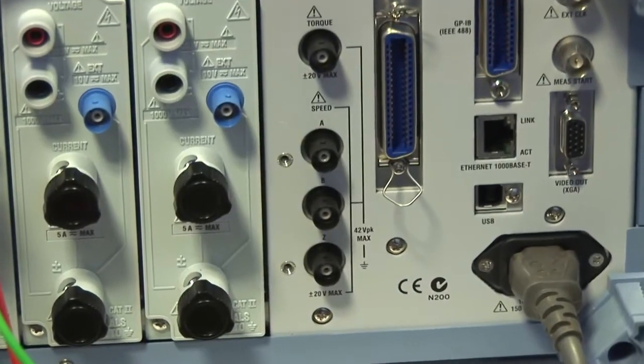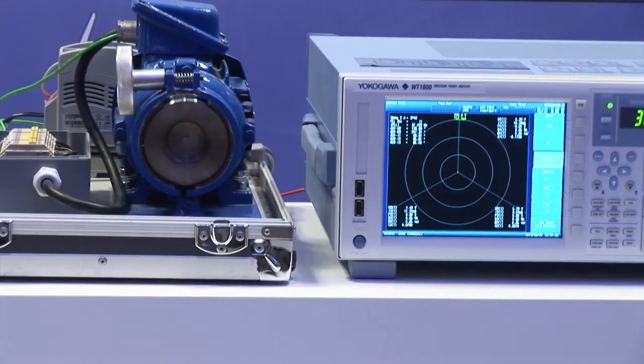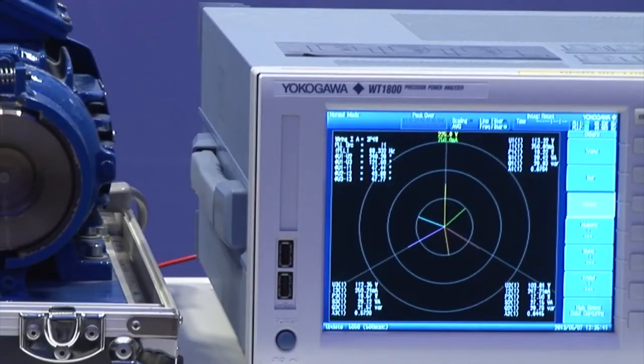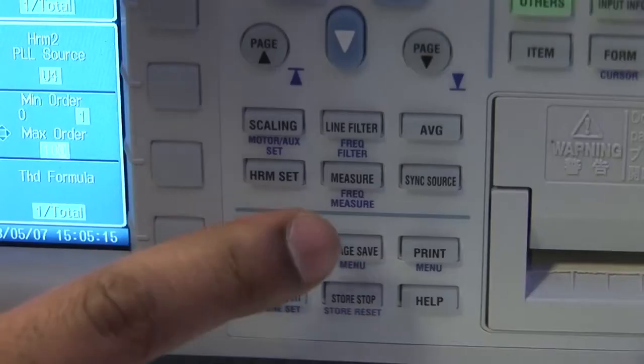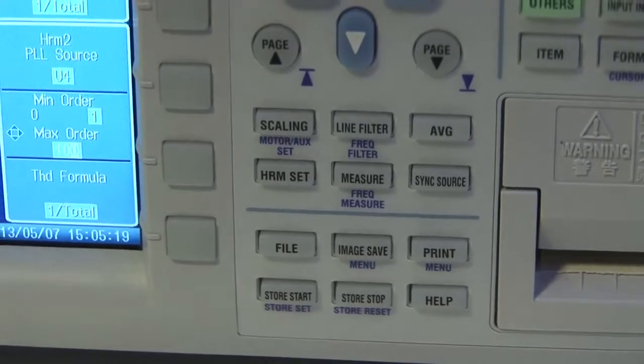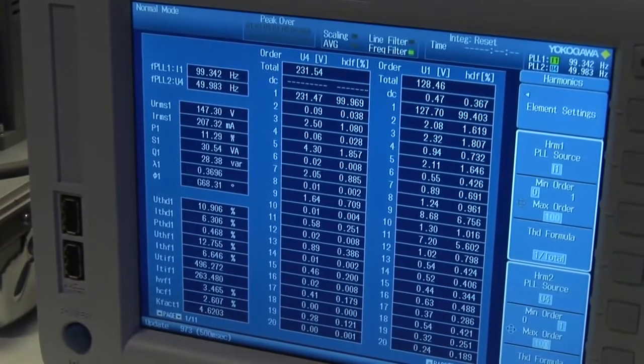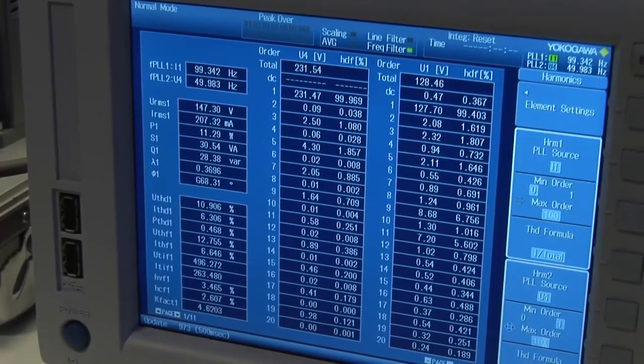The A, B and Z speed inputs of the motor function makes it possible to detect the rotation direction and measure the electrical angle of the motor. The high precision harmonics option allows the simultaneous measurement of harmonic components and the total harmonic distortion along with the conventional RMS voltage and current values.